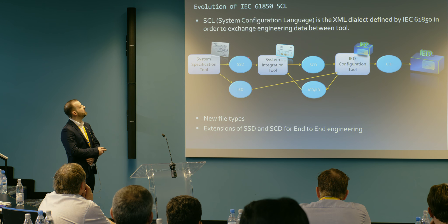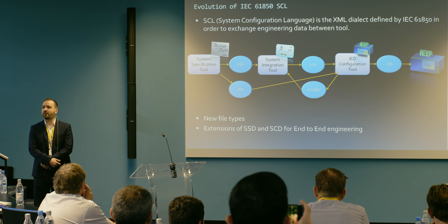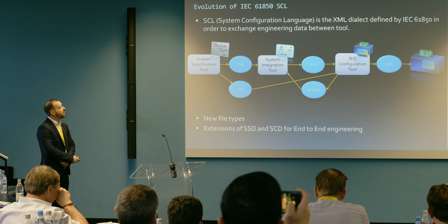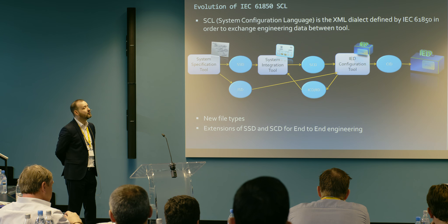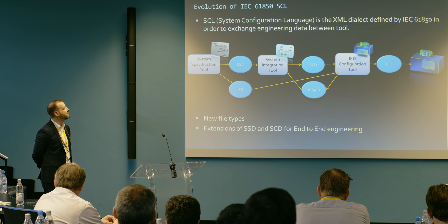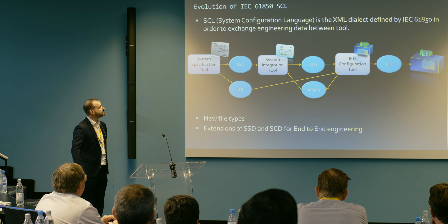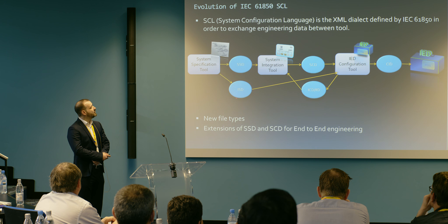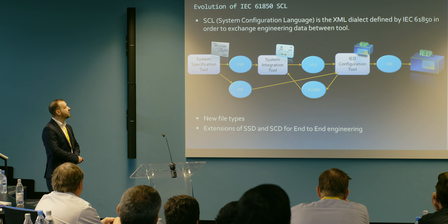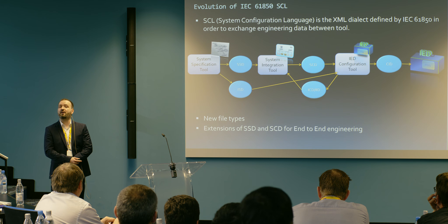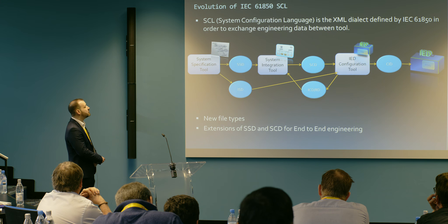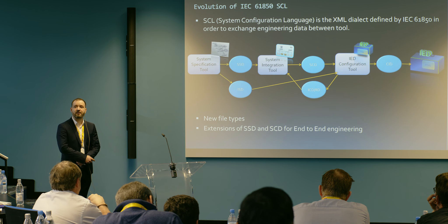In the system specification description, you will find information on the electrical process, but also on the data used in the form of logical node references. The SCD file then augments the specification and the electrical process with actual intelligent electronic devices that implement the electrical process. The ISD is a proposed new file type — the IED Specification Description — a description file you can use to vet if a given IED matches your requirements, useful in negotiating frame agreements or acquisitions.